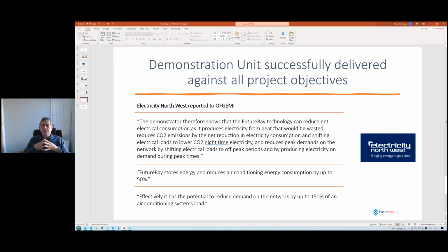The other one was we actually use phase change in the cold tank. We produce ice in a storage medium, and the storage of ice can be quite expensive. So we came up with our own solution, which I'm not going to share the details of at this stage, but it was very low cost and very effective. So the storage medium were the two areas where we needed to make sure we had our understanding correct. Because we're using effectively off-the-shelf equipment, yes it needs tweaking, it needs honing for our need, but we expected those to work as they worked.